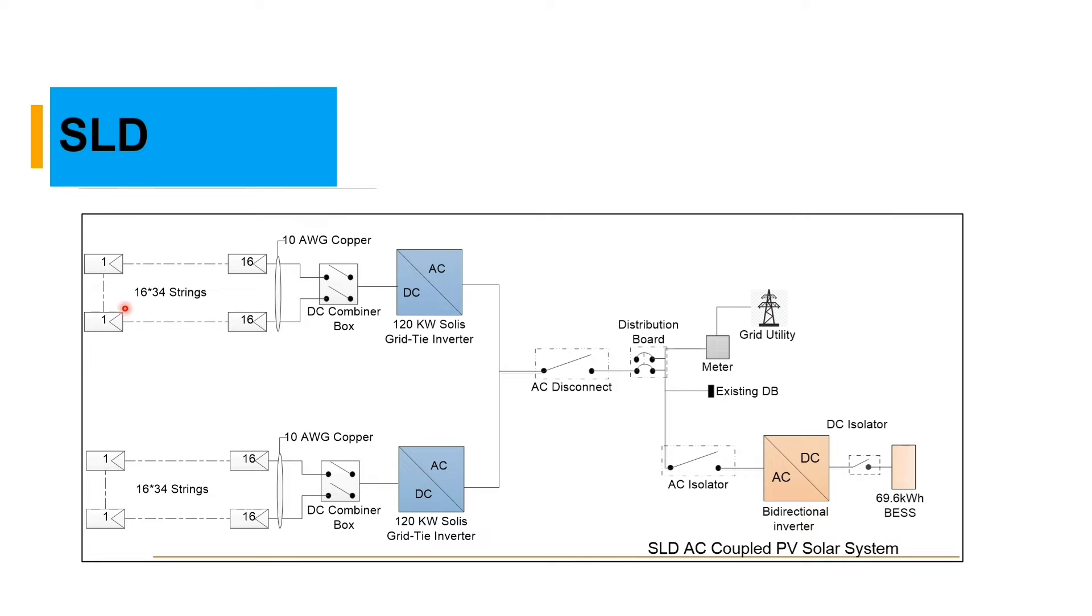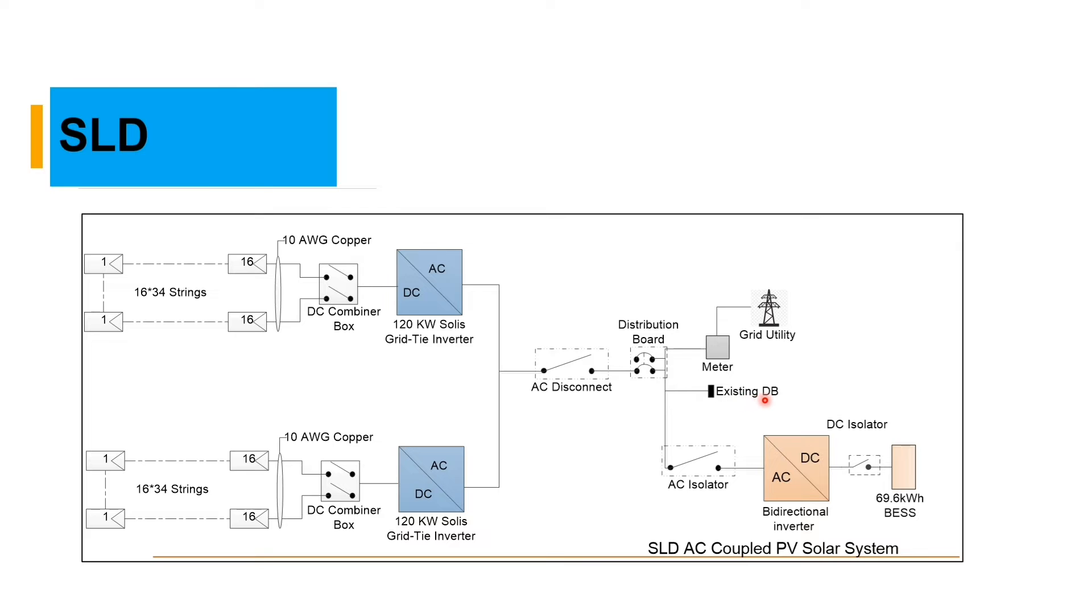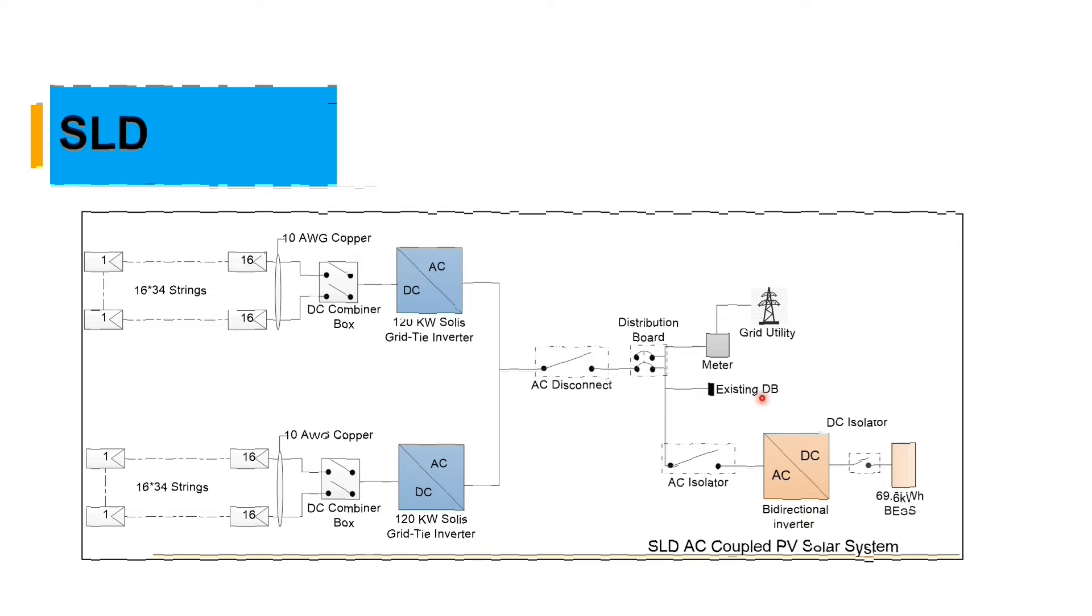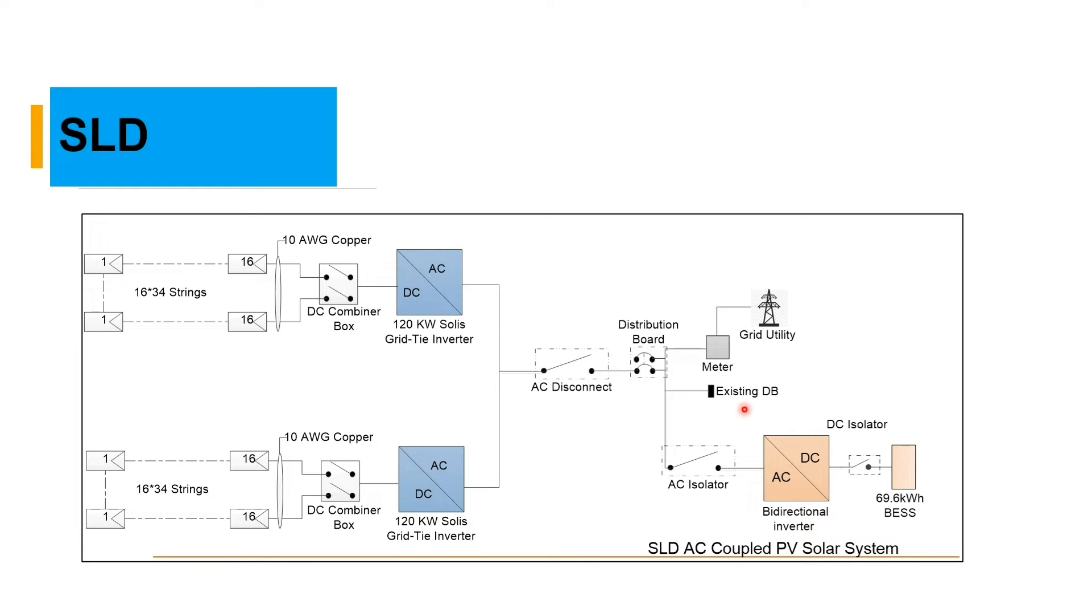Here we have our detailed single line diagram, which we have 16 panels in series and 34 strings. We have our DC combiner box, we have two inverters 120 kilowatt and 120 kilowatt which goes to the AC combiner box. In the AC combiner box we have our AC isolator of our bi-directional inverter which is the 35 kilowatt and we have our battery of 69.6.